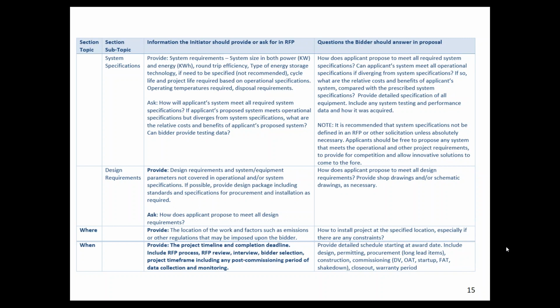You have to have the electrical infrastructure to get that system tied to the grid, and that all needs to be designed. You need all the relaying in place, disconnect switches, breaker panels, the whole distribution, point of connection, conduit installation, cable and wire installation, communication cabling and conduit. If you're building a pad or a building, you need all the civil work done, all the concrete work done, all the grounding done.